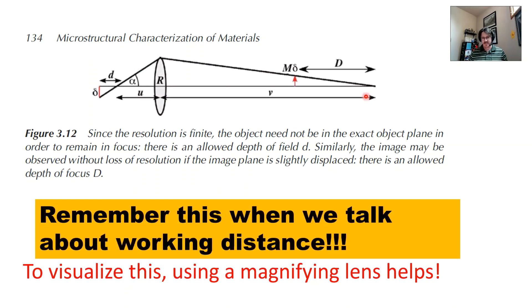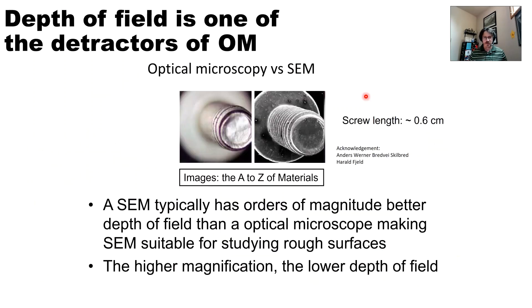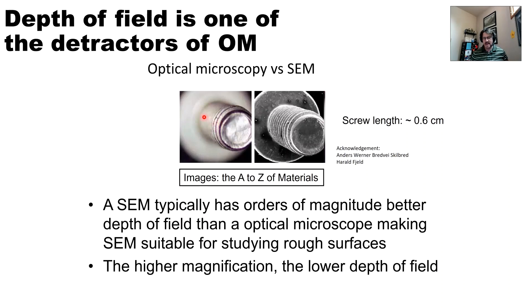Depth of field is one of the detractors of optical microscopy. Looking through an optical microscope at a screw, you can get a nice image of the top of the screw but you lose everything else - the depth of field is very poor. SEM has a much greater depth of field, which is one reason to use SEM even at lower magnification. There are optical systems that take images at different focal planes and stack them for greater depth of field, though that's more labor intensive.